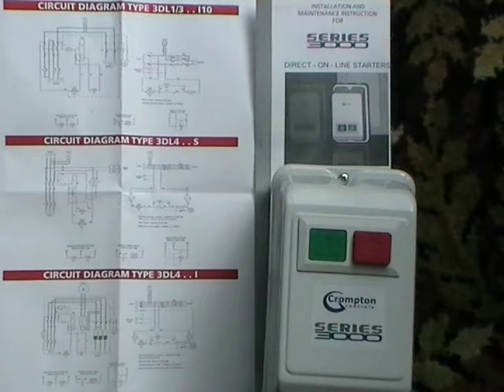So, having taken out the circuit breaker on the generator, and as the generator is effectively a motor in reverse and has the same overload protection needs as a motor, one of these red and green button motor starters is ideal to protect the generator and yet still allow the generator to provide its maximum current for short periods of time.